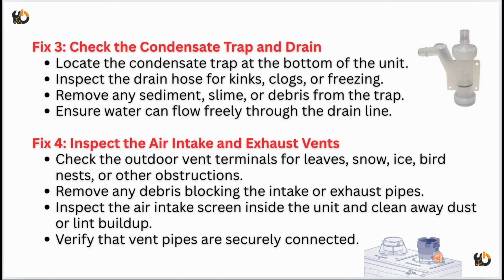Fix 3. Check the condensate trap and drain. So locate the condensate trap at the bottom of the unit and inspect the drain hose for kinks, clogs and freezing, and remove any sediment, slime or debris from the trap. Ensure water can flow freely through the drain line.